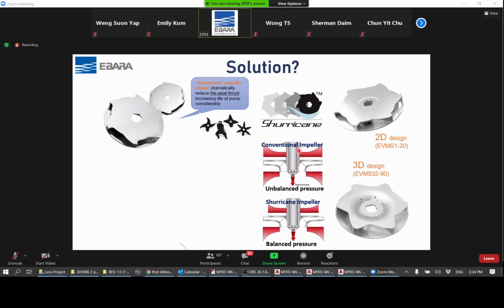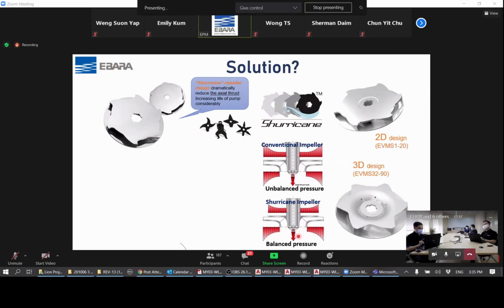Unbalanced pressure between the top and the bottom, but with the Shurricane impeller, it is able to reduce the pressure at the top with this special shaped impeller surface and allows the pressure to be equalized between the top and the bottom. Very, very smart move. So you can see the design of, let's say, a smaller model and a bigger model and how the shape of the impeller is. So only Ebara has this design method for all the impellers.